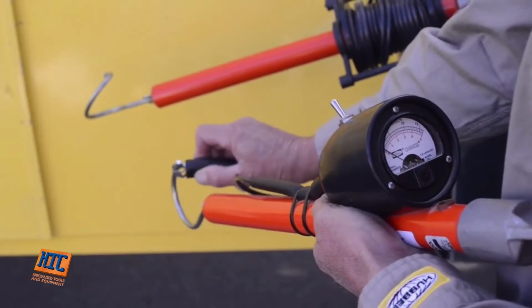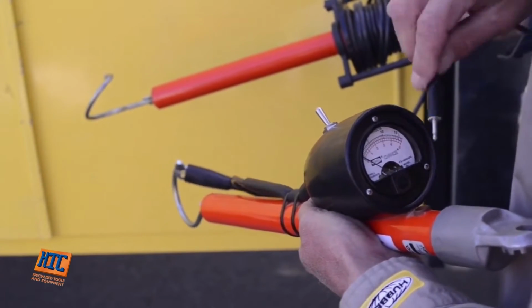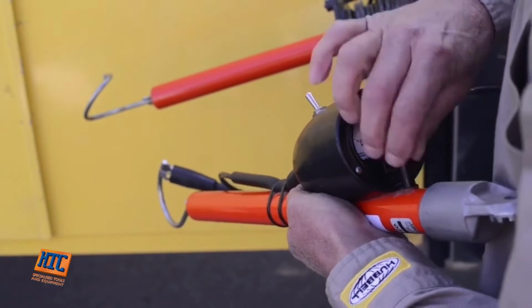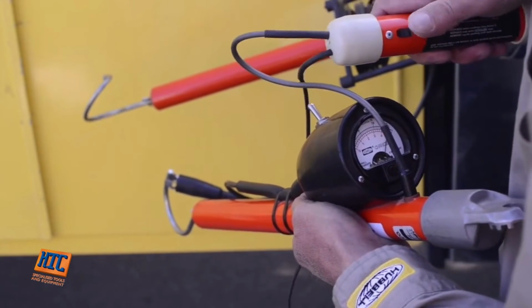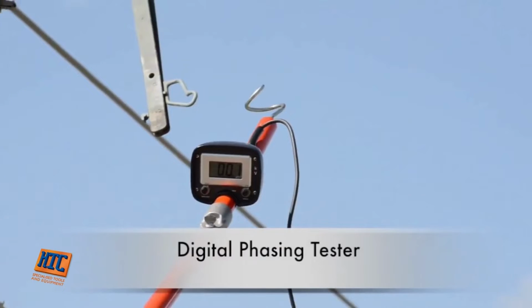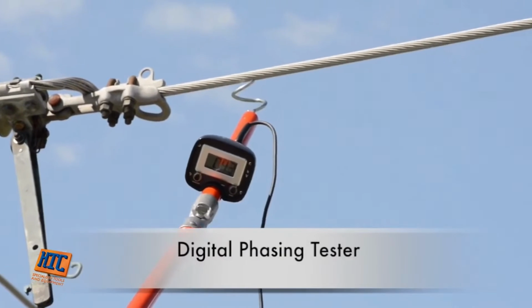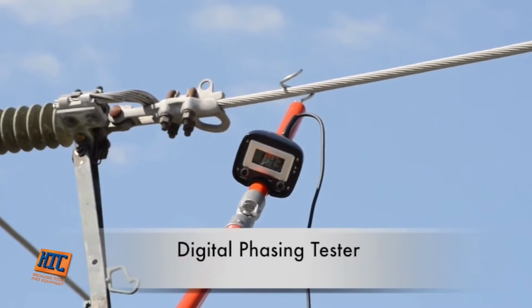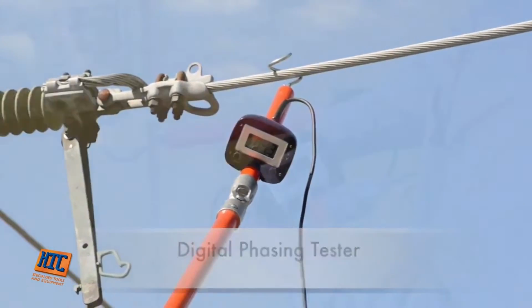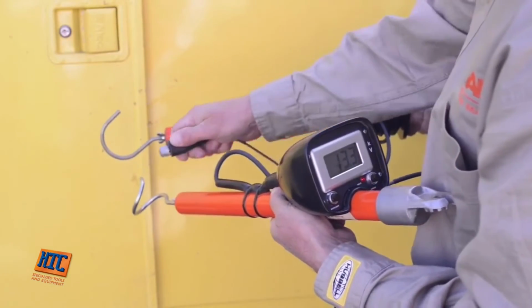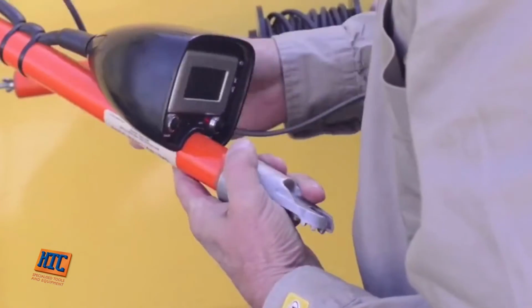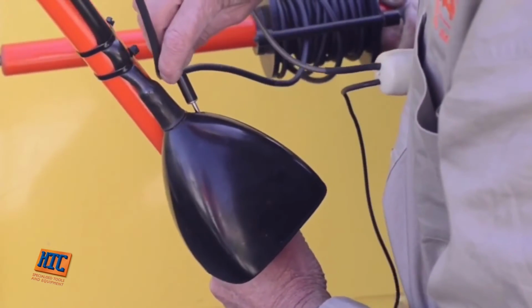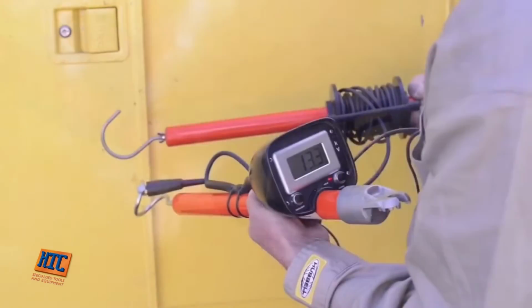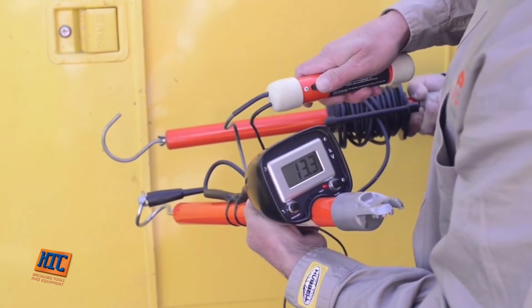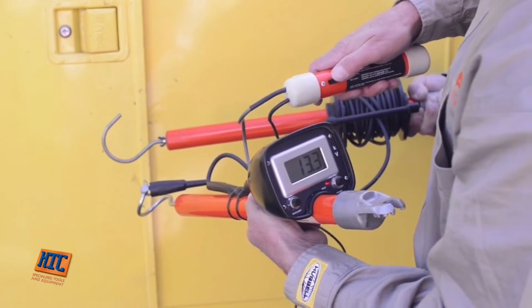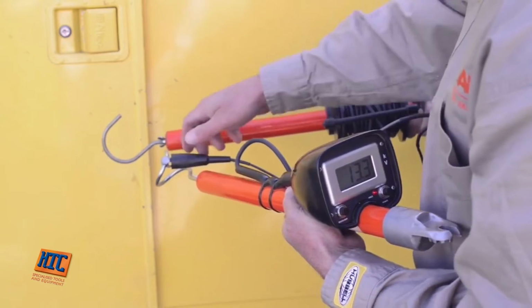After each use, verify the phasing tester is still fully functional, again using the voltmeter tester specified in the instructions provided with the phasing tester. For determining phase relationships, the Chance digital phasing tester works essentially the same as the analog phasing meter. To pre-check the digital phasing tester for operable condition, use the phasing meter tester specified in the instruction manual. Connect the alligator clip onto the hooks, then insert the probe into the back of the phasing tester housing. This pre-check must be performed before each use.